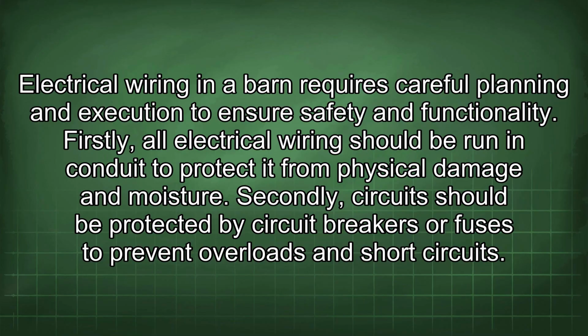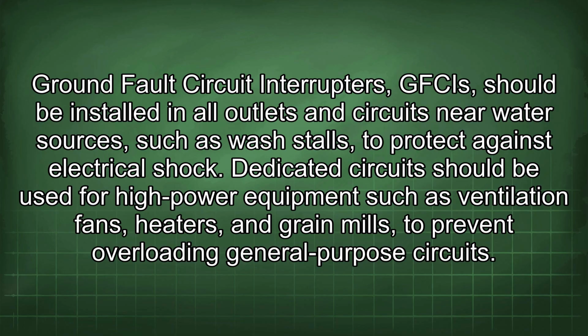Electrical wiring in a barn requires careful planning and execution to ensure safety and functionality. Firstly, all electrical wiring should be run in conduit to protect it from physical damage and moisture. Secondly, circuits should be protected by circuit breakers or fuses to prevent overloads and short circuits. Ground fault circuit interrupters, GFCIs, should be installed in all outlets and circuits near water sources such as wash stalls to protect against electrical shock.